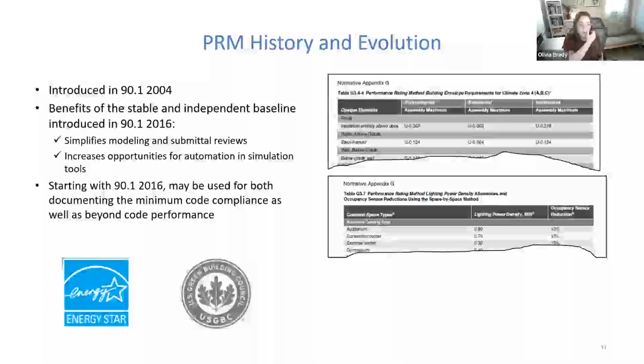Okay, so we talked a bit about the history and evolution of 90.1. Now I want to sort of hone in on the performance rating method. It was first introduced in 90.1-2004 as a methodology for quantifying performance of designs that substantially exceed the minimum requirements of the standard. Then in the 2016 edition, the methodology underwent some very significant changes.